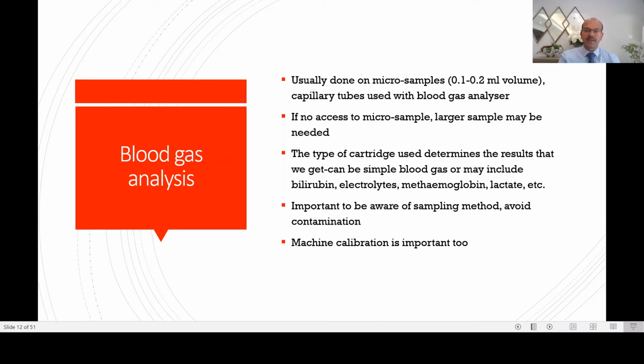When you do have a blood gas analyzer, you should be familiar with what type of cartridge you are using in your unit, and the type of cartridge we use determines the result we get. Of course, you cannot change it every now and then because the calibration will be linked to the type of cartridge you use. So on a predominant basis, you have to choose the one which will be most suitable for you. And you do have the options to add separate tests. We can discuss, of course, the cost increases when you add certain parameters.